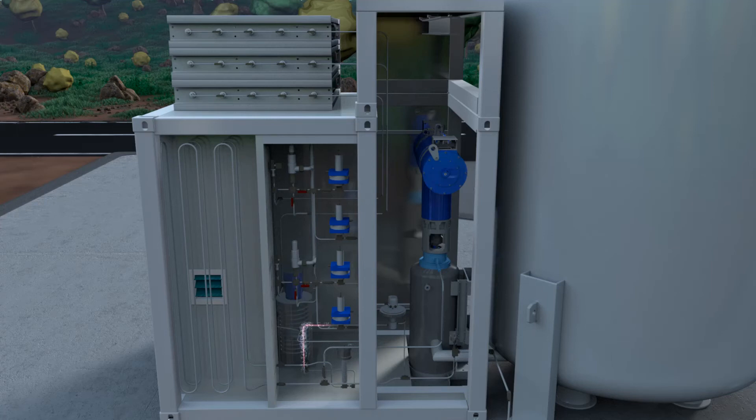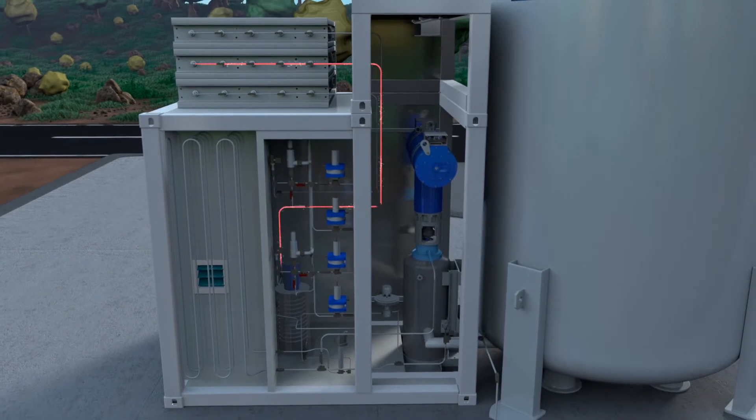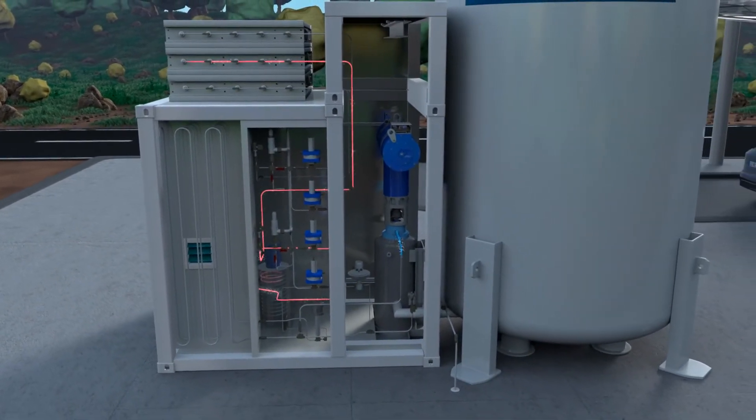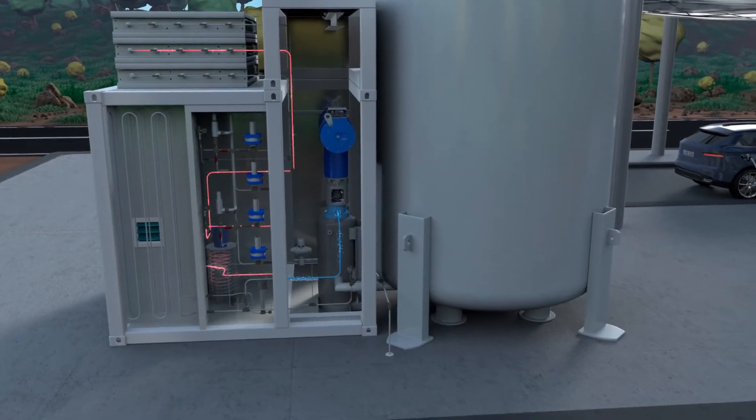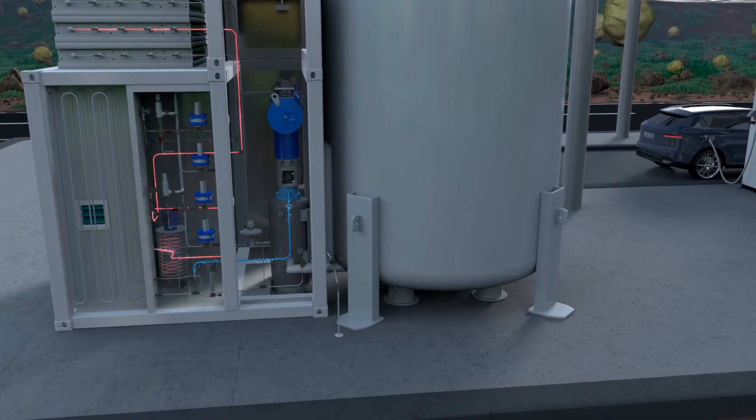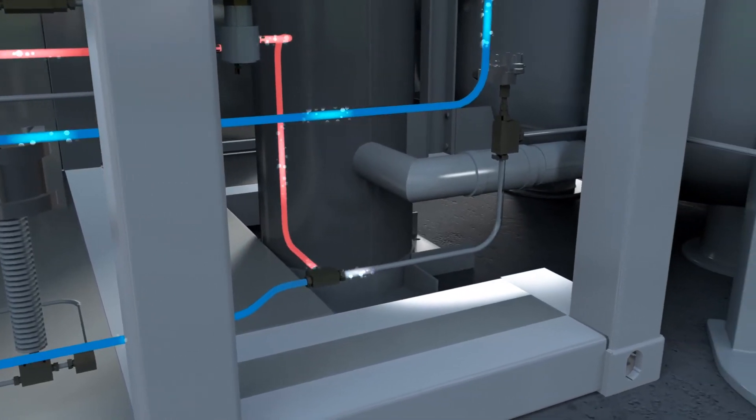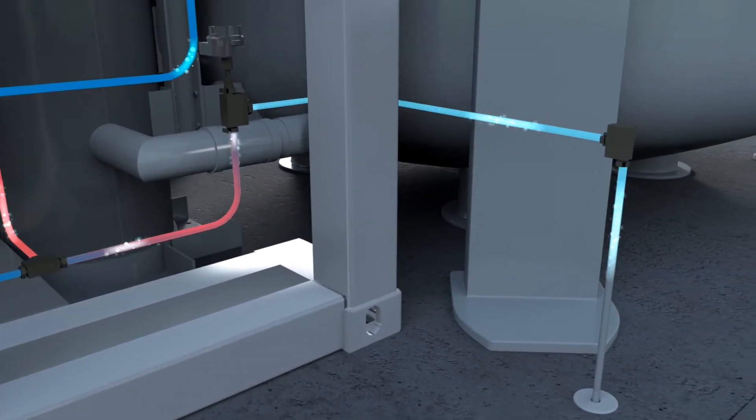After that, the hydrogen starts flowing towards the vehicle from both the pump and the storage tanks. At a temperature of approximately minus 220 degrees Celsius, the gas from the pump is still cryogenic. The hydrogen from the storage tanks, however, is at ambient temperature. When mixing the hydrogen from both sources, this difference in temperature is utilized to achieve the perfect hydrogen fueling temperature of minus 40 degrees Celsius.